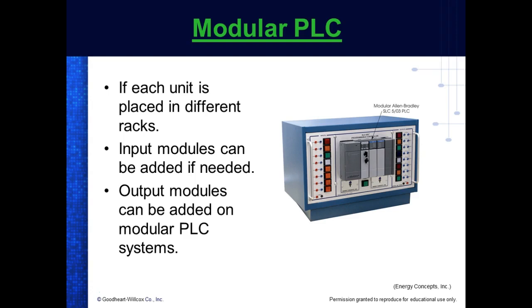And we'll see that. And then what you do is you buy modules. We can't rip these out, guys, because they're wire tied down. But you buy modules depending on what you want. So this guy right here's got 16 inputs and 16 outputs. But if I wanted to expand it, what could I do? I could add another module. If I wanted to add analog, I could add another module. So this guy's got 1, 2, 3, 4, 5, 6. It's a 7-slot rack. We call this a rack. It's a 7-slot rack, but one of them is eaten up by your CPU. That means I got 6 modules.